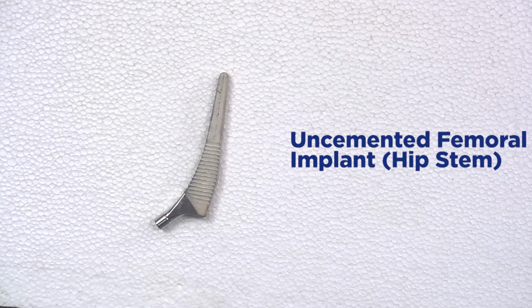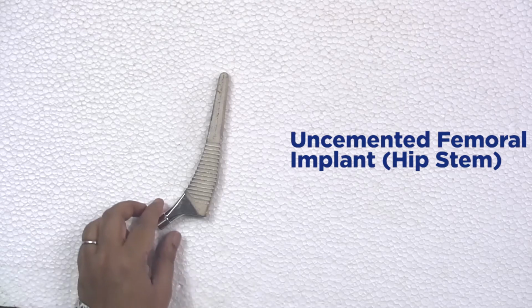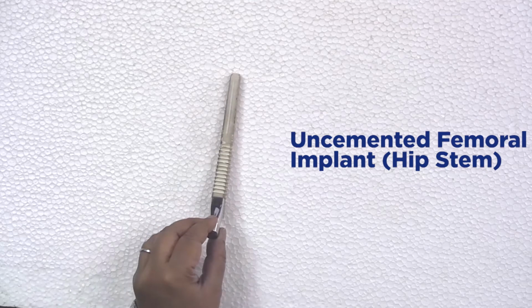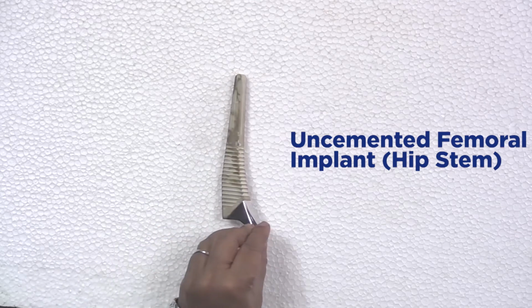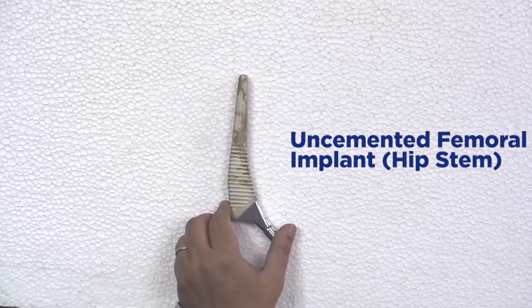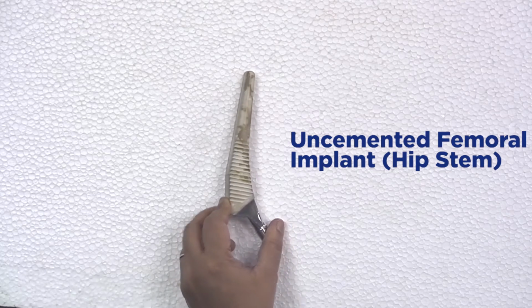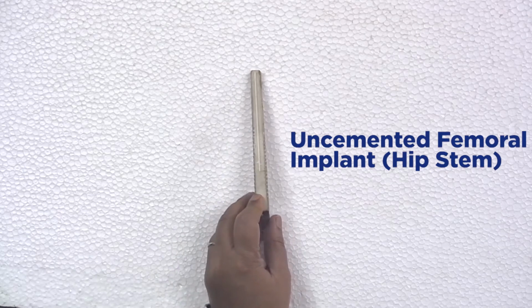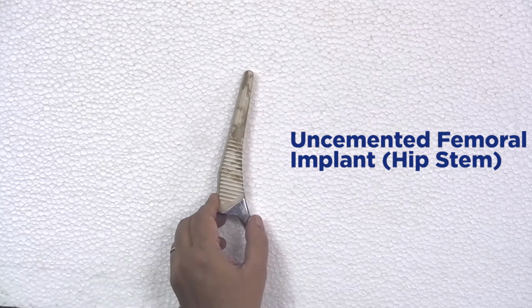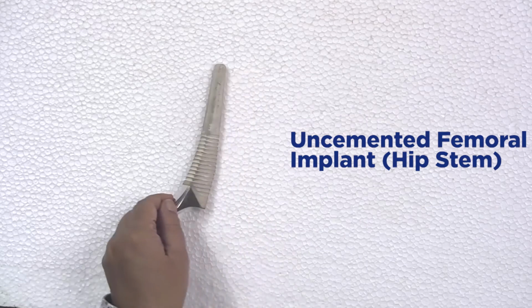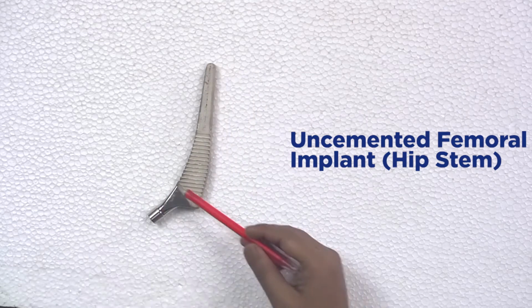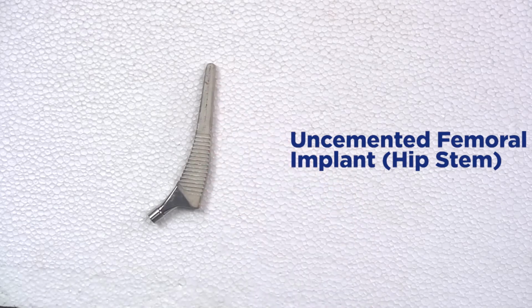Let me turn it around so that you can see the prosthesis fully. The stem has a rough, coated texture that helps biological fixation with bone.